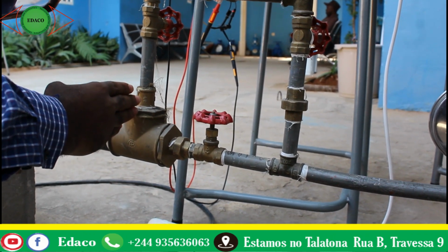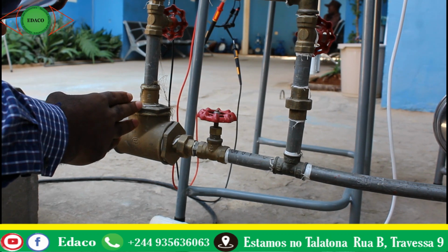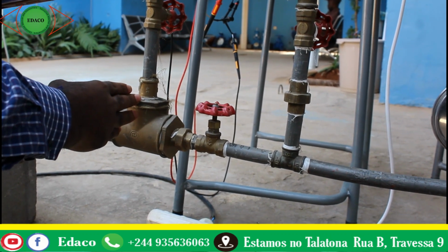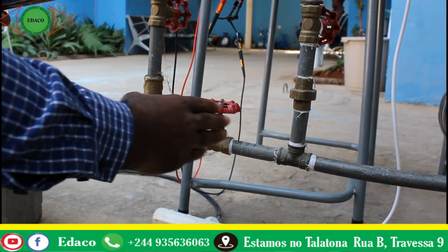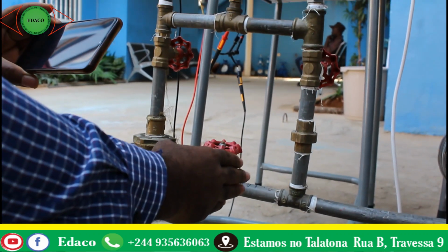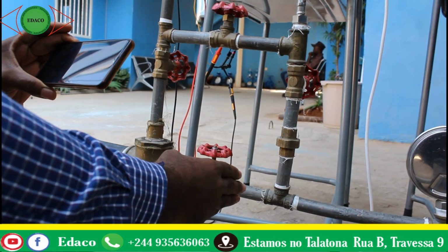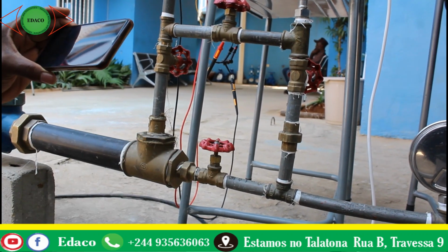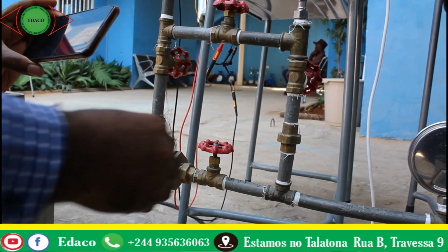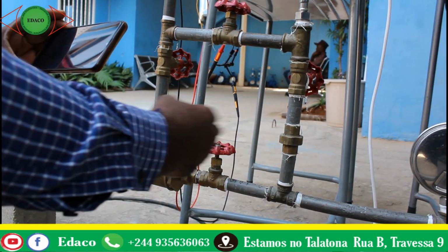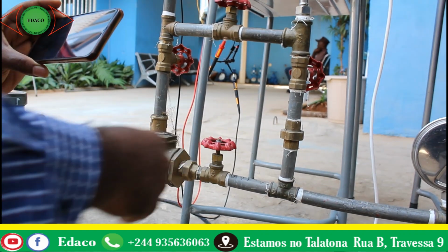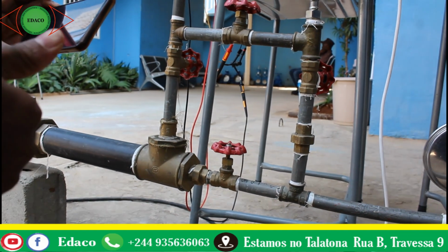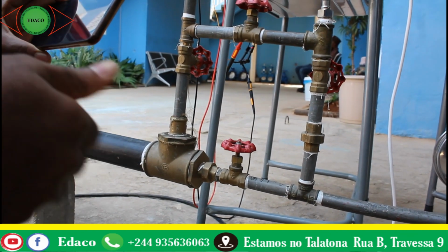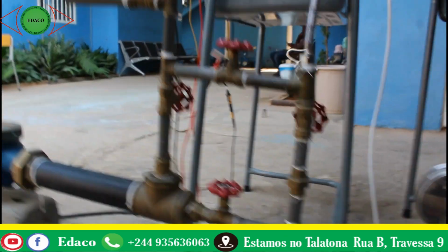We will have a higher pressure on this side but a lower velocity, and a lower pressure on the smaller side of the pipe but a higher velocity. So by measuring the difference in pressure between the two sides, we can get our flow rate through the system. This is what we are doing.